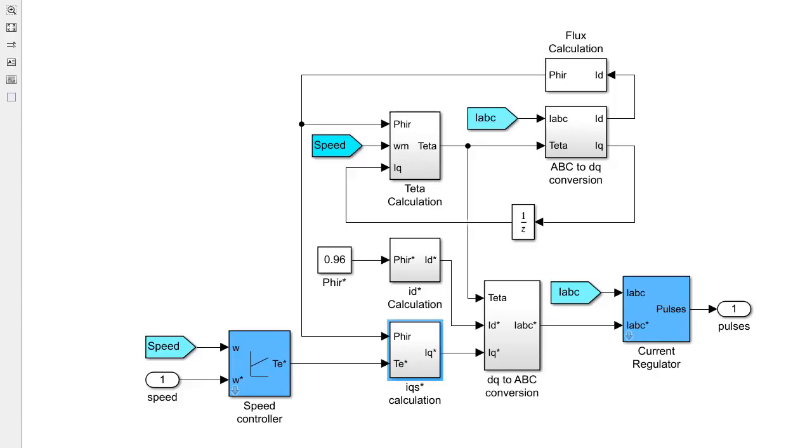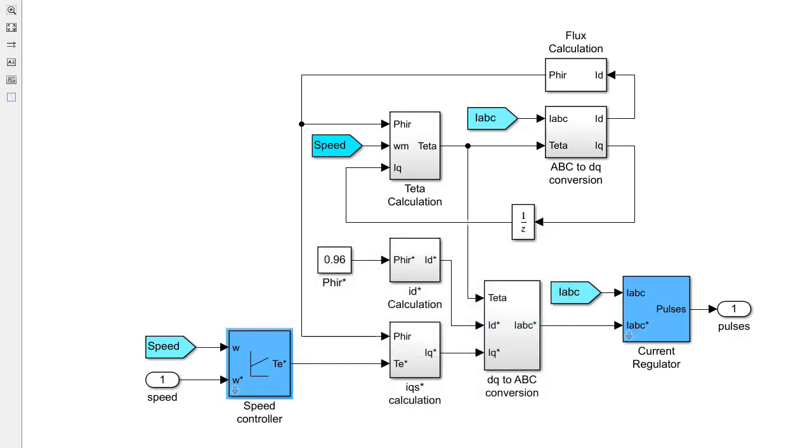In this control system design, similar to PMSM control, a cascade feedback and feedforward control system is configured for velocity control. This simulation shows the speed control system configuration of a typical industrial induction machine drive. In the drive control systems, there are two PI controllers to control the d-axis and q-axis stator currents and one PI controller in the outer loop to achieve the speed control of the motor.